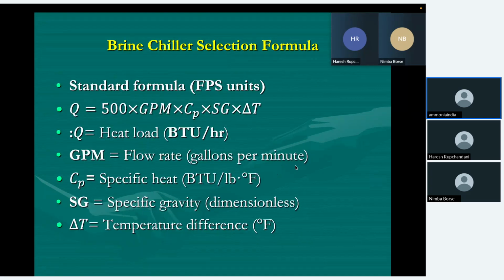The brine chiller selection formula, if we use it in BTU unit, now since we are following BTU, I said let us follow in BTU also. As I told earlier, 500 is the formula, 8.33 into 60, that is Q = 500 into GPM into specific heat into SG, that is specific gravity, into delta T. Q is the heat load in BTU per hour. GPM is flow rate in gallons per minute.